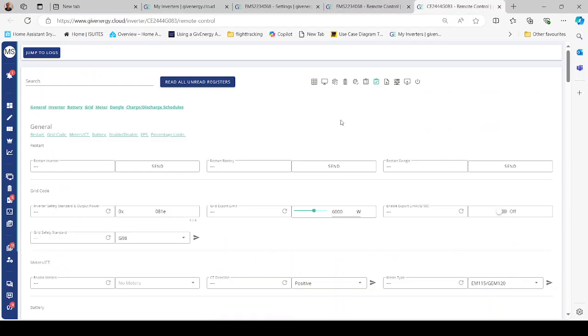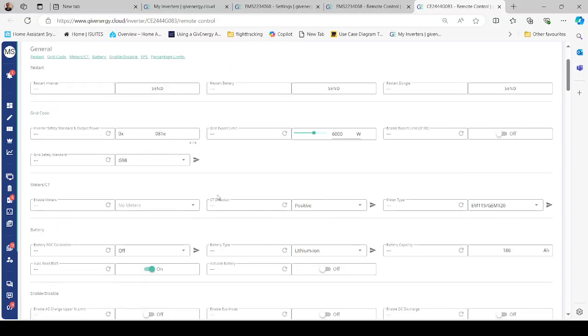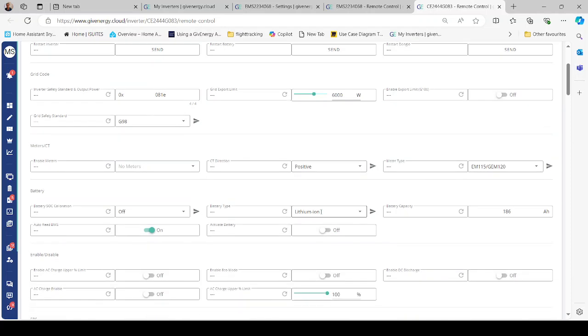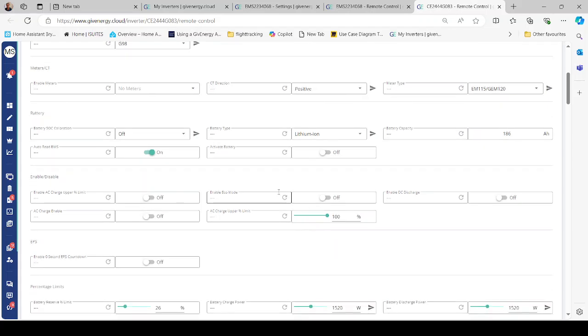Inverters and inverter settings. I've seen on many occasions that the inverter settings have been changed. That's sort of a slight misunderstanding of how the inverters work with an EMS. The important part here is that meters are set to no meters. The inverter does not have any meters. It has an internal CT that it will use to read the grid. Generally, we have eco mode turned off, discharge mode turned off, and AC charge turned off. The EMS will take control of those when it needs to and will turn them on and off.